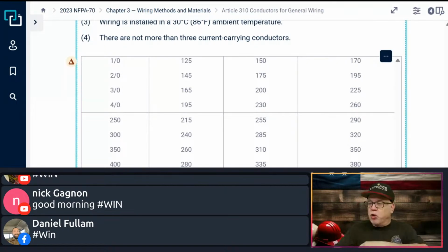In the real world, if you want to run a 600 and size a raceway for that, you do you, if that's what you want to do, then you go for it. But typically, the best option is to try to keep things under 500 kcmil. So I'm going to see if there's a better result if I parallel it. Don't be afraid of paralleling.